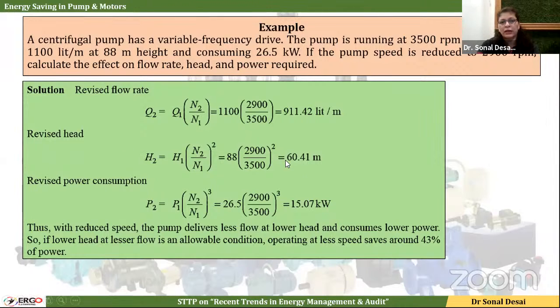So if it is okay to have lesser head, then we can adopt this variable frequency drive, because we can see that by reducing speed, the pump delivers less flow and lower head. But at the same time, power consumption, which is 15 compared to 26, is 45% lower. Hence, we are directly reducing power consumption by almost 50%. So if an oversized pump was selected, or a load variation is there, such as a cooling tower, or a day-night variation, then go for VFDs. Also, if you are continuously running a pump for more than 4,000 hours per year, and you are varying the load by 20 to 30%, a thumb rule says that use of a VFD is always good, because it will have a payback of less than 1 year.